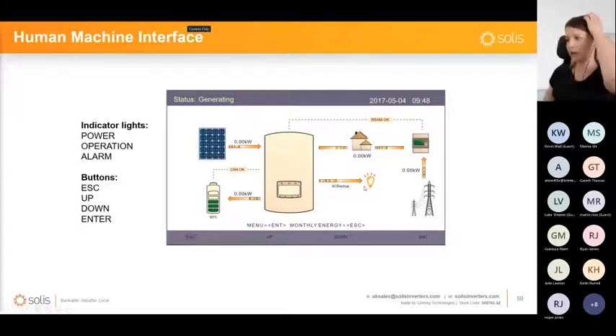A lot of customers are a little bit confused, because if they don't have anything connected to this backup port, they're still going to see it, and they might even see a very small measurement error, a few watts going to this. So in order to stop these questions from their side, this port should actually be disabled, and it should disappear from here. That can be done in the control parameters. I'll show you a little bit later in the menu of the inverter.